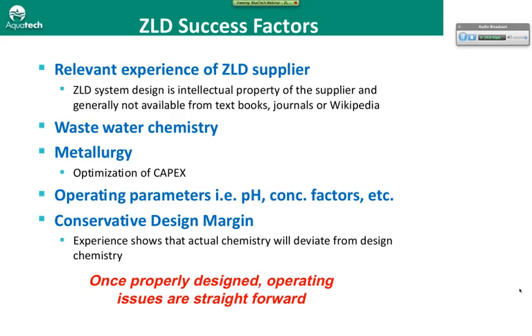As far as success factors for a ZLD system, it's very important to go to a supplier with relevant experience. As Michael explained, the intellectual property or experience of the supplier is very important. Design guidelines generally aren't available from textbooks or journals, and you won't find it on Wikipedia. It's important to understand the wastewater chemistry, starting with where it's coming from. In many instances we have experience with that industry, but it's best to have a good design basis for the chemistry, and to look at the ranges of chemical constituents so we have a conservative design.